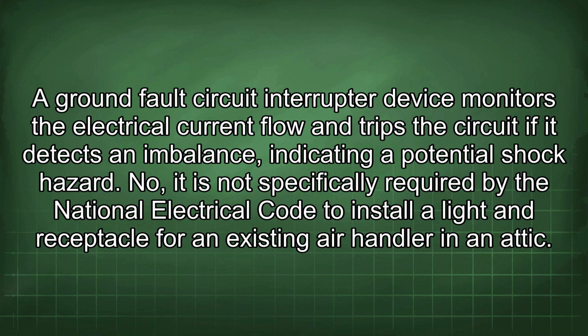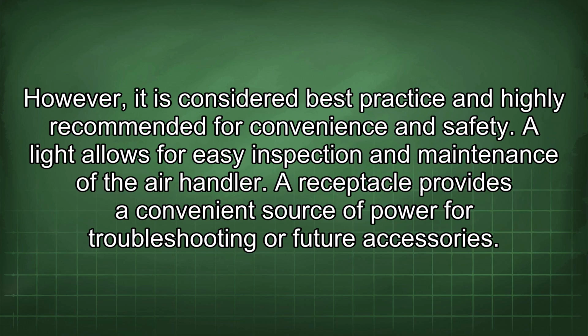No, it is not specifically required by the National Electrical Code to install a light and receptacle for an existing air handler in an attic. However, it is considered best practice and highly recommended for convenience and safety. A light allows for easy inspection and maintenance of the air handler. A receptacle provides a convenient source of power for troubleshooting or future accessories.